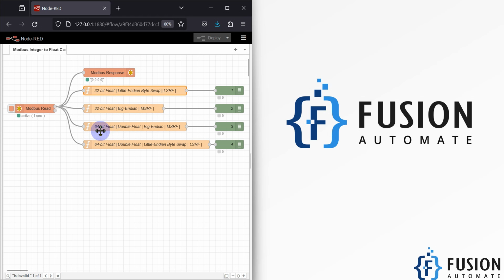The 64-bit float, also called double float, has a Big-Endian type, most significant register first. And the last one is 64-bit floating point values, also called double float, a kind of Little-Endian Byte Swap, which is least significant register first.